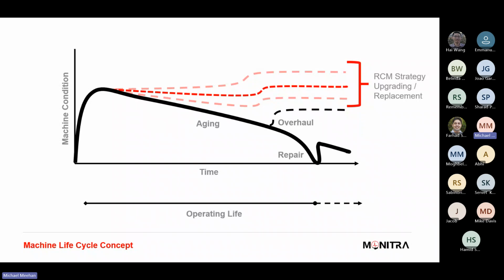Partial discharge systems. And now there are online solutions for that, where you can take an online measurement, but not only that, you can have a permanent online system which will give you the ability to really correlate operating parameters with PD parameters and actually see the formation of PD maybe earlier due to the correlation of the other parameters, which is really what we will look at in some ways today. Obviously, bearing condition monitoring and alignment checks are other benefits of an RCM program, which basically turn that curve from being more downward sloping to more horizontal.